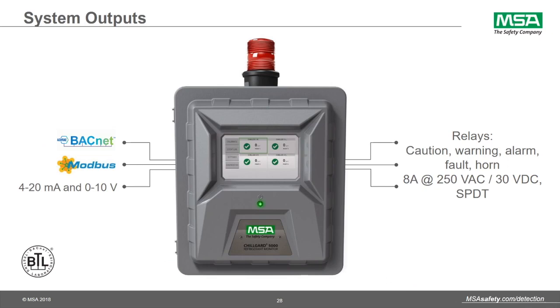Having flexibility in system outputs is critical, whether it feeds back to a building management system or it acts as standalone. The Chillgard 5000 ships with native BACnet or Modbus, as well as analog or voltage options. It also comes with 5 8-amp relays that provide 3 levels of alarm. Also provides a fault relay and additional horn relay. The Chillgard 5000 is also BTL listed, and that's a BACnet third-party verification.